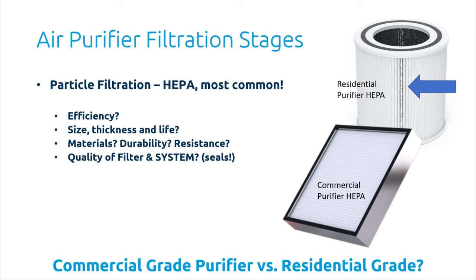The questions you want to ask are: how efficient is it? Well, if it's true HEPA, it's 99.95+ percent efficient on a first pass. What is the size and thickness of it? How long is it going to last? A residential one is going to be pretty thin, a commercial one is probably going to be pretty thick. How long is it going to last? The quality of the filter system and seals — the seals are super important. You can have a system with the best filter in the world, but if the seal isn't tight, it's not going to act like it's supposed to.